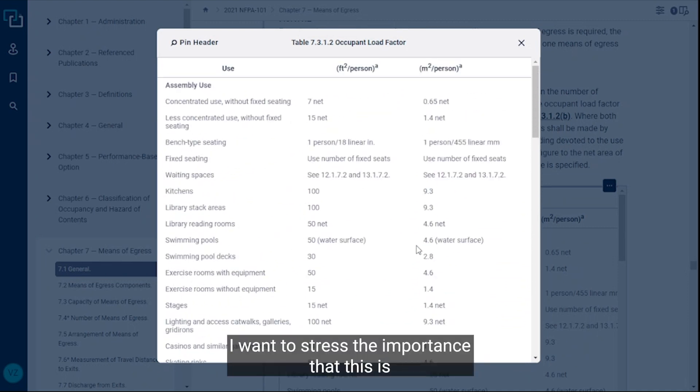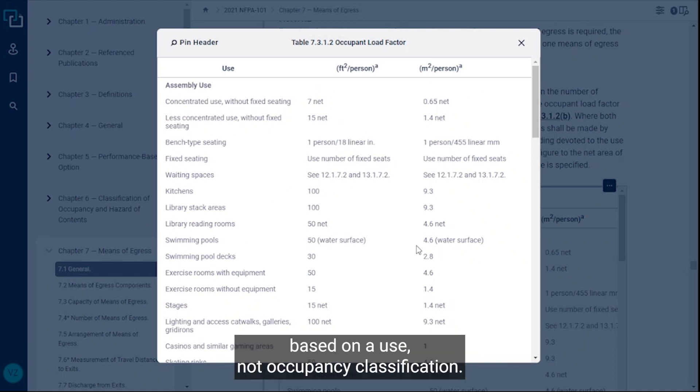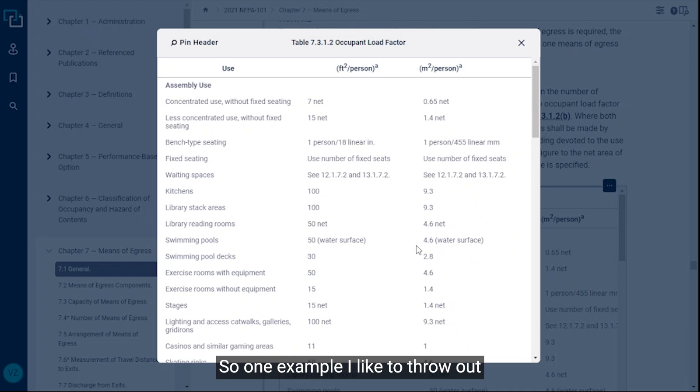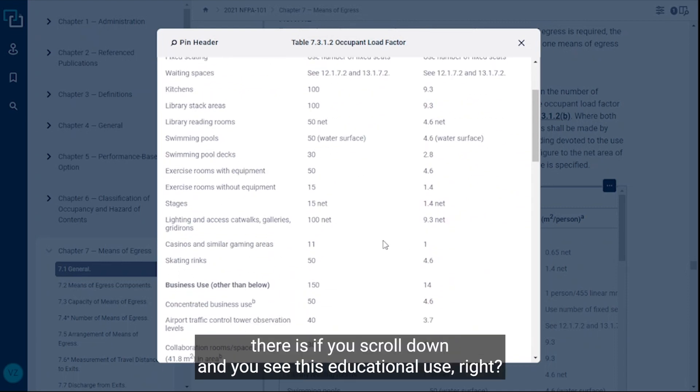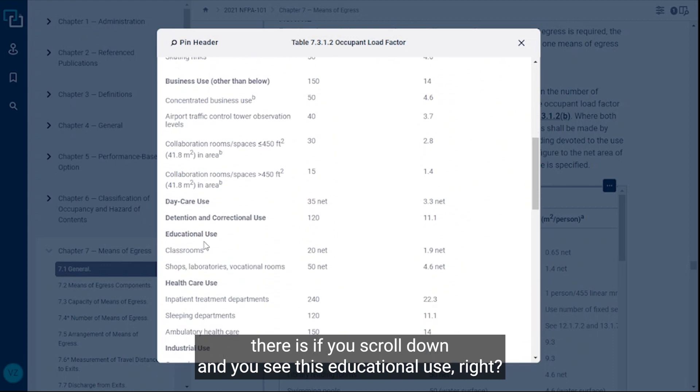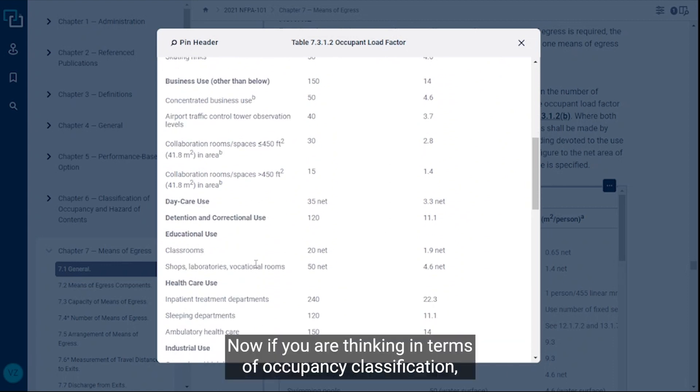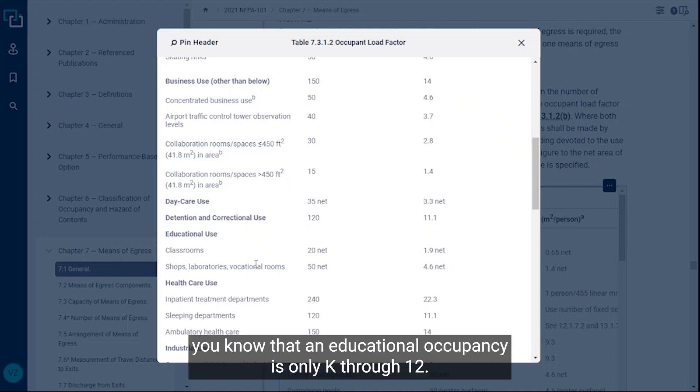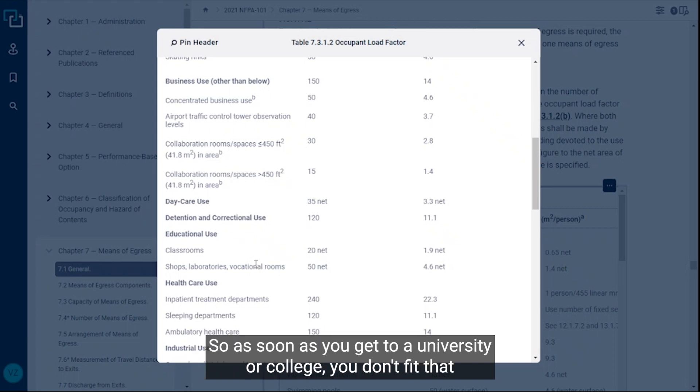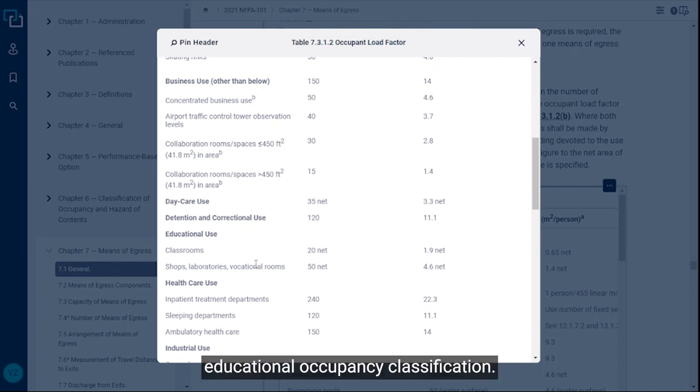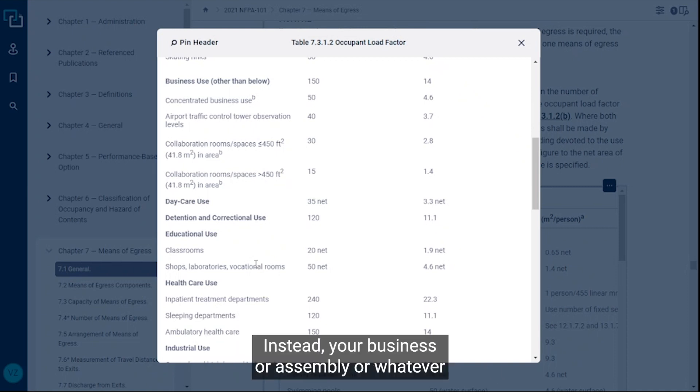How do you use this table? I want to stress the importance that this is based on a use, not occupancy classification. You're looking at how a particular space is used. One example I like to throw out there is if you scroll down and you see this educational use, we have classrooms. If you were thinking in terms of occupancy classification, you know that an educational occupancy is only K through 12, so as soon as you get to a university or college you don't fit that educational occupancy classification. Instead you're business or assembly or whatever it may be depending on how that space actually serves.